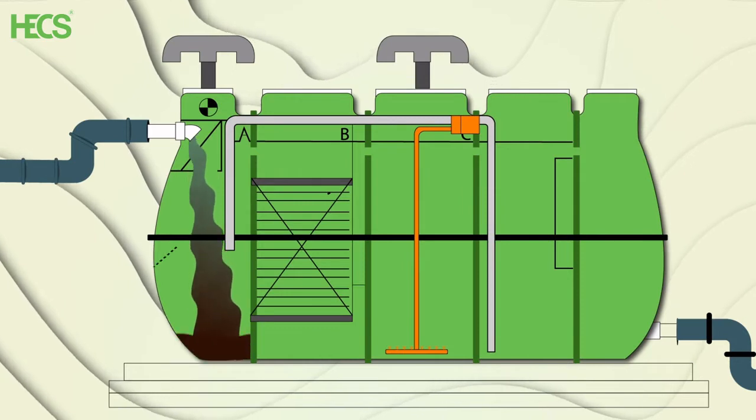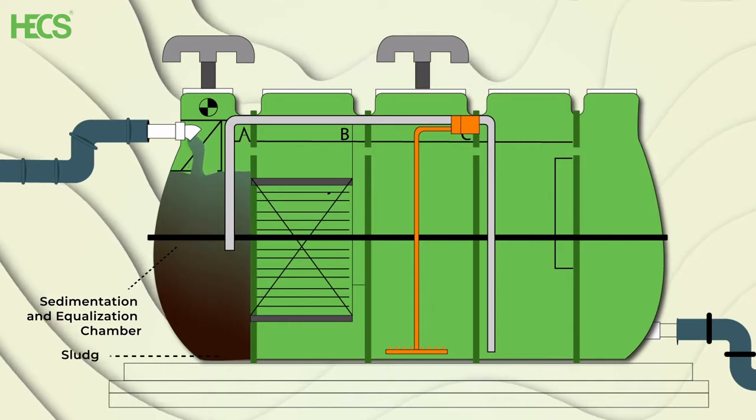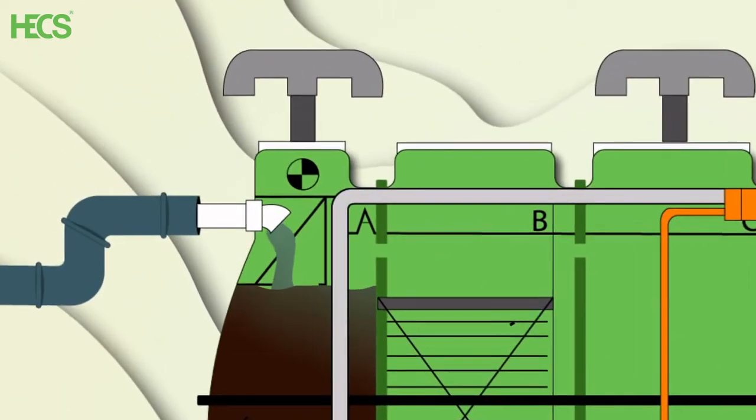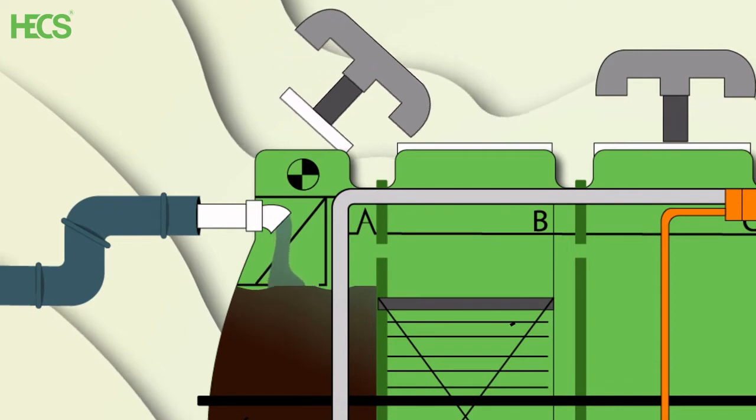The sewage flows through the screening chamber into the sedimentation and equalization chamber. Particles of higher density, that is sludge, will settle down at the bottom of this tank through gravity. This sludge accumulates at the bottom and can be easily desludged through the first manhole. Desludging is generally required once in four to six months.